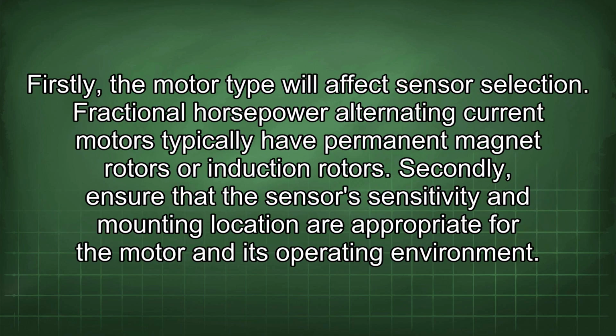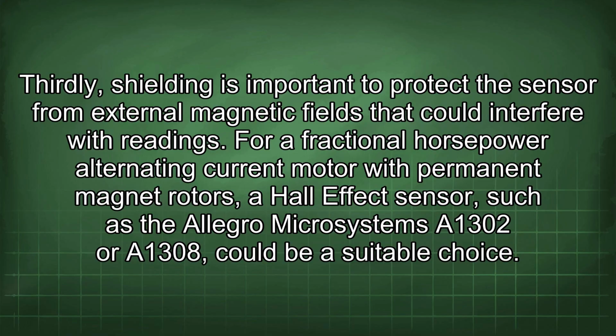Firstly, the motor type will affect sensor selection. Fractional horsepower alternating current motors typically have permanent magnet rotors or induction rotors. Secondly, ensure that the sensor sensitivity and mounting location are appropriate for the motor and its operating environment. Thirdly, shielding is important to protect the sensor from external magnetic fields that could interfere with readings.